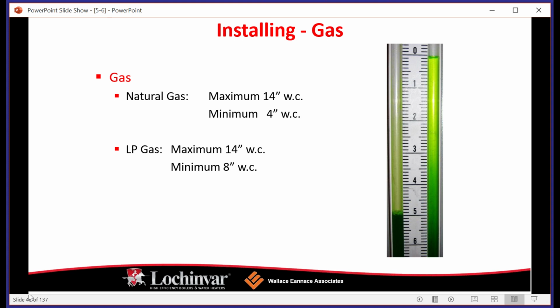You're no longer going to have your static, you're going to have your dynamic, and you're going to watch that inches of water column drop through the floor, and you're going to have issues. So what you want to see ideally is somewhere in the 7 to 10 range, I think, a 7 to 10 static range. So when the boiler or water heater does fire and starts consuming that energy, you can drop some inches of water column, you're still going to be within the threshold, which is going to allow you to make your proper BTU input.